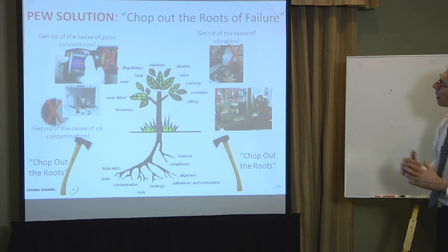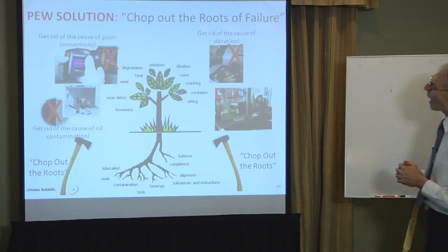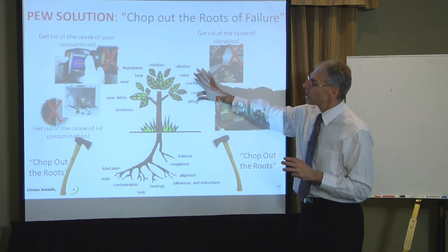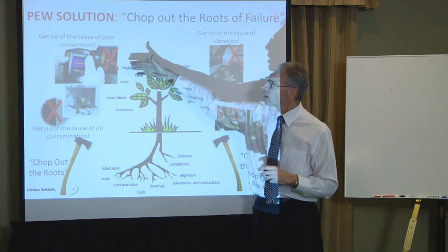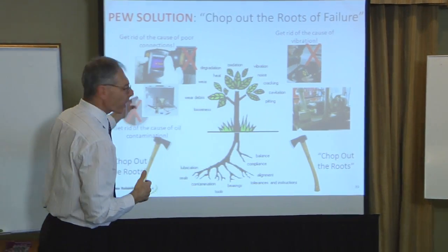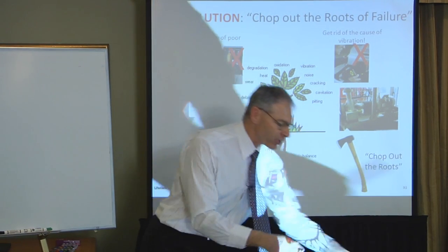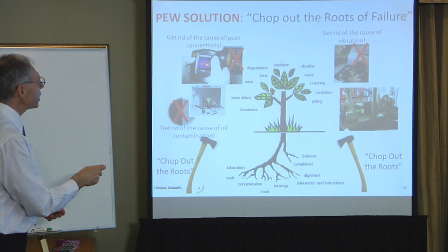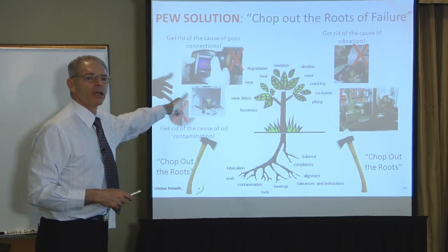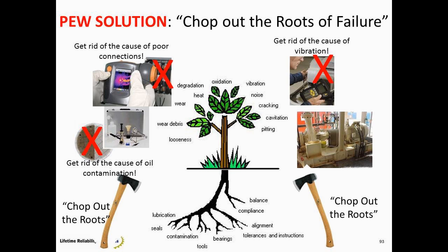So back to this particular diagram here with my failure tree, and if we work at this level here, for example, our thermography camera, good technology, very low cost technology for condition monitoring, this is wonderful. Now this one here has done us a great service. It's picked up this hot joint here, and now we can fix it. I can fix this hot joint. The trouble is that hot joint is now going to require a shutdown. I'm going to require maintenance costs. I'm going to have to stop the plant from producing for a period of time.